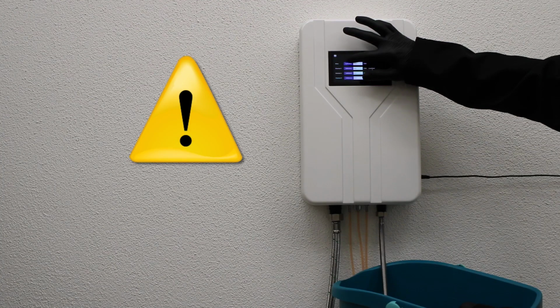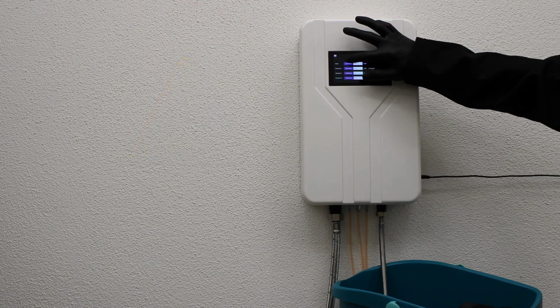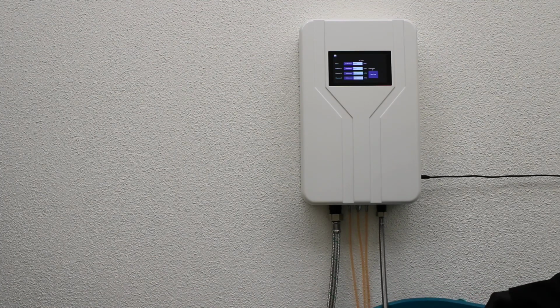It is recommended to regulate the water flow with a pressure regulator to 5 liters per minute for dosages below 3% of the chemical and to 3 liters per minute for dosages above 3% of the chemical. Hold the output hose of the dosing system firmly in the bucket, as the system will run water into the bucket for 30 seconds once you initiate the calibration. Please note that the calibration process cannot be interrupted. When you are ready, press the Calibrate field next to Water in the calibration section. The dosing system will now dispense water into the bucket for 30 seconds and then stop automatically.